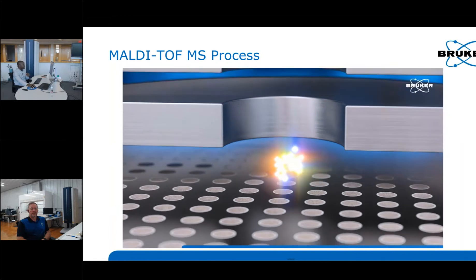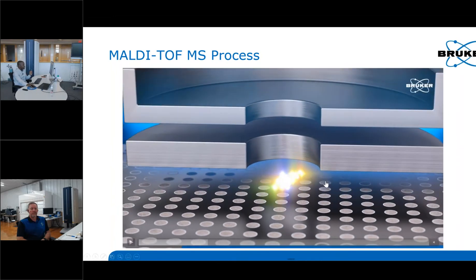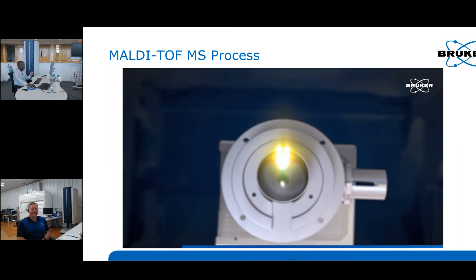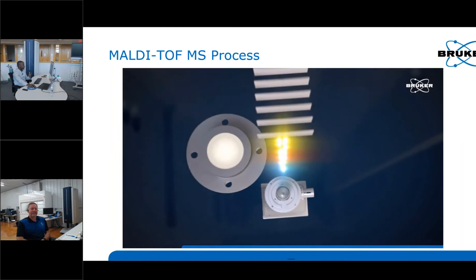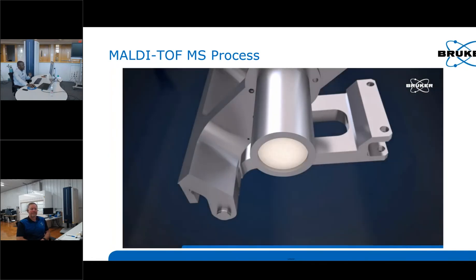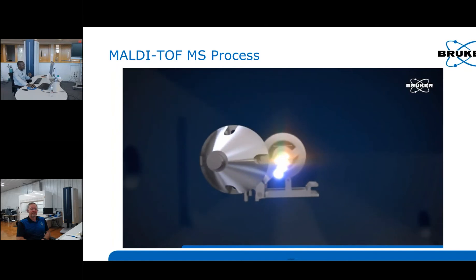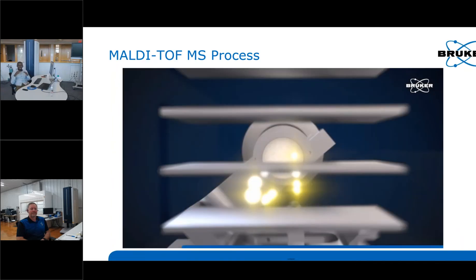After the ionization step, high voltage is applied on the target plate to accelerate ionized particles or ionized molecules to the detector. That's the first step — the ionization step. The next phase is time-of-flight mass spectrometry, in which the ions separate by mass because you have a constant voltage across the whole plate and a constant flight tube where the ions fly all the way to the detector.